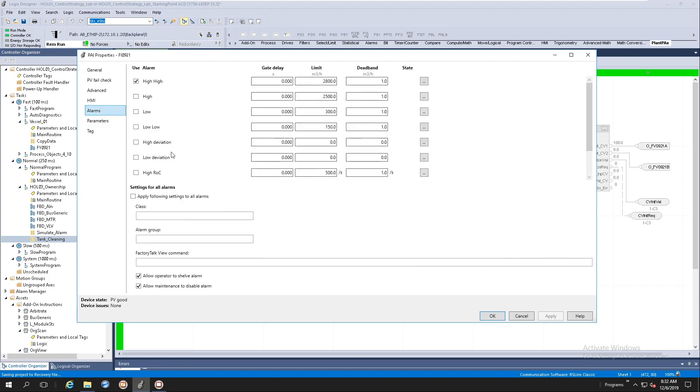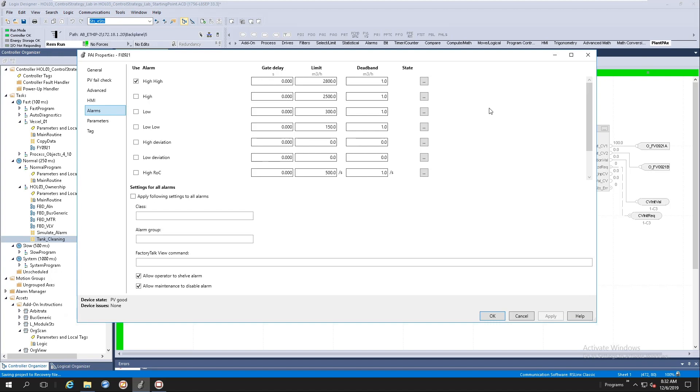All right, let's talk about alarming. Our library of process objects native to the controller are now utilizing the logic tag-based alarms that was introduced in V31. So when you instantiate an instruction, you will by default get all these alarms. And when you start doing your alarm rationalization process, you will enable alarms that you require and start doing the configuration at that point in time. So you don't have to instantiate all your instructions anymore, run it through the alarm builder tool, generate the XML content and input that into your HMI server. It's now all part of the instruction and it's enabled by default.